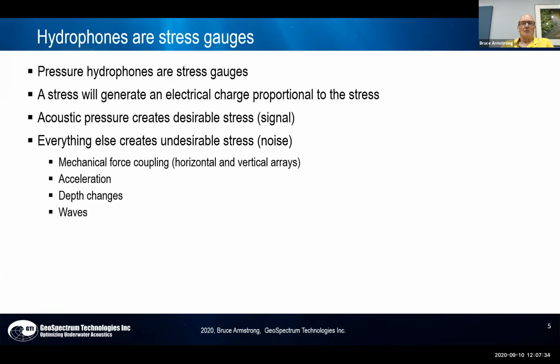So the one thing that you really need to know is that hydrophones are stress gauges. That's all they are. If you put stress into the ceramic, you're going to get a charge out of that ceramic that's proportional to the stress. So it's a linear device. The acoustic pressure creates a desirable stress. That's the signal you're looking for. And everything else creates undesirable stress. So if you have any mechanism that is stressing the ceramic, it doesn't know that it's not acoustic, and it's just going to generate charge and you get noise.